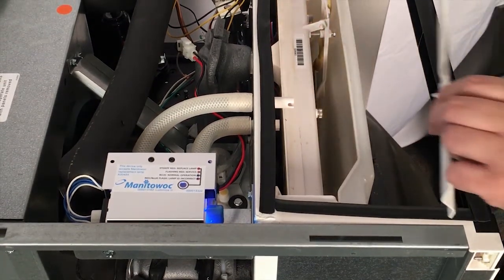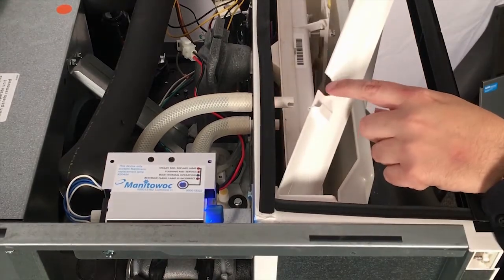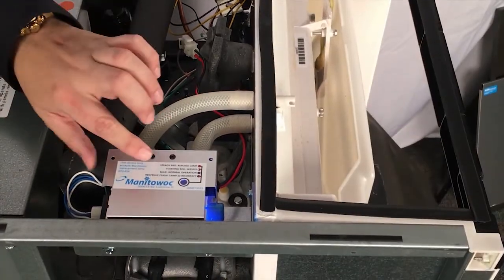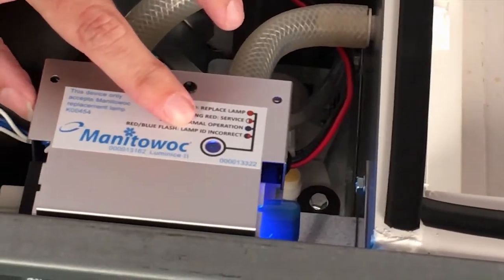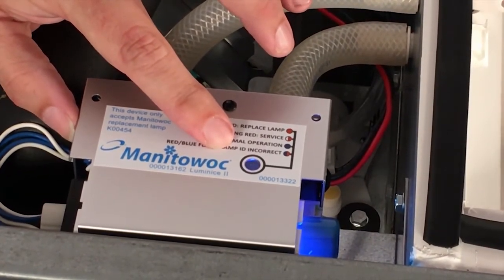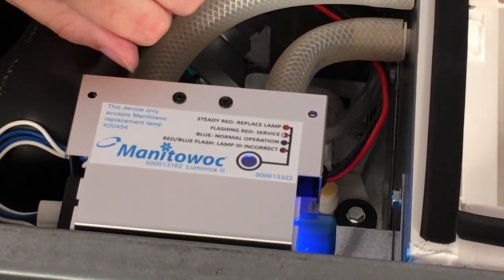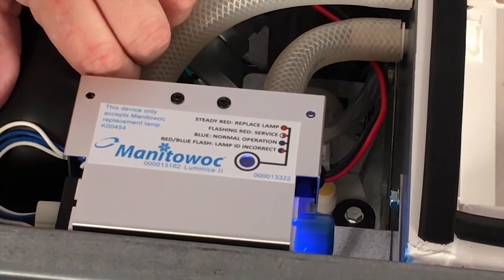Once that's all in place, you can put the cover back on that's supplied with the LuminIce Kit. It has a little groove cut out for those tubes in it and it just snaps into place. On the top of the LuminIce unit, there are service diagnostics built into it — it has lights telling you if it's in good order or if the bulb needs to be replaced. A blue light means it's in good order, a flashing red-blue light means there's a problem with the unit, and a red light means it's time to replace the bulb or there's a problem with the unit.